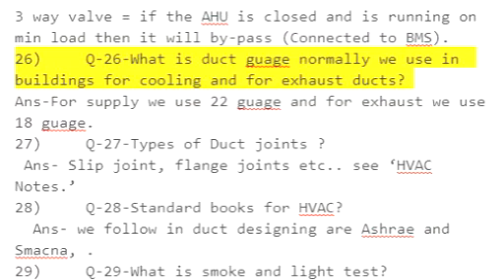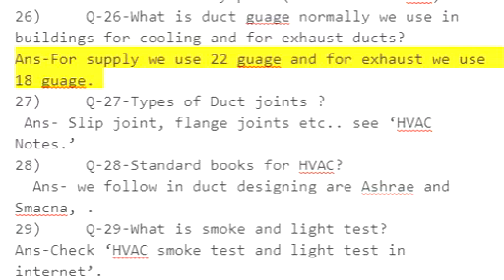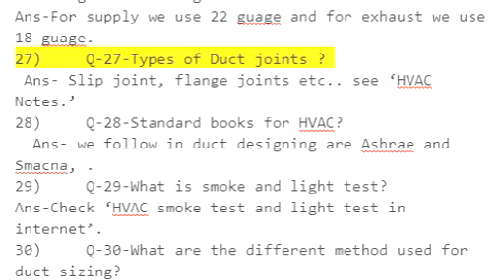Q26: What is duct gauge normally used in buildings for cooling and for exhaust ducts? Answer: For supply we use 22 gauge and for exhaust we use 18 gauge.